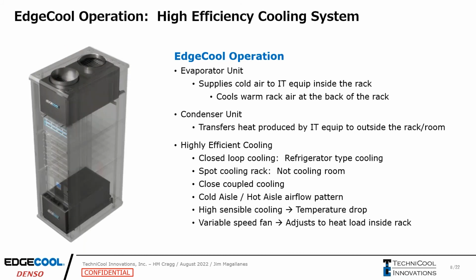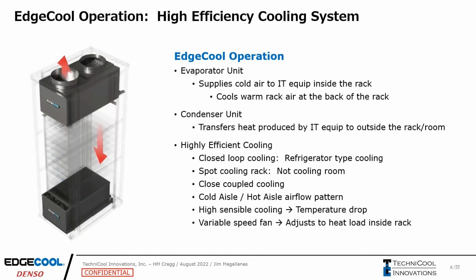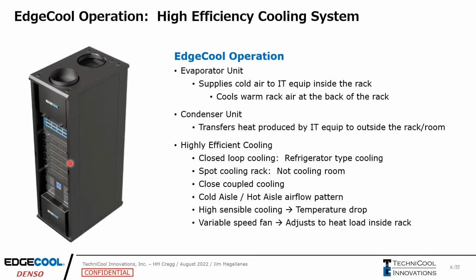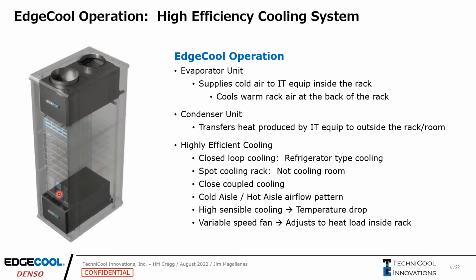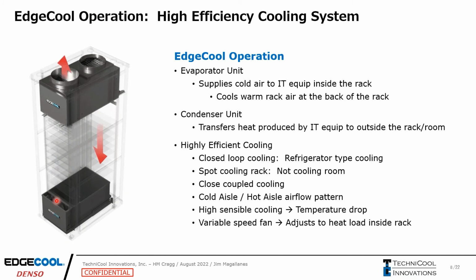And lastly, we have a variable speed fan in there, meaning that the evaporator unit has a fan in there that can go from 100% of airflow volume all the way down to 30% airflow volume. So depending on the heat load within the rack, our fan system will adjust to that heat load, so we can match that heat load a little bit better.